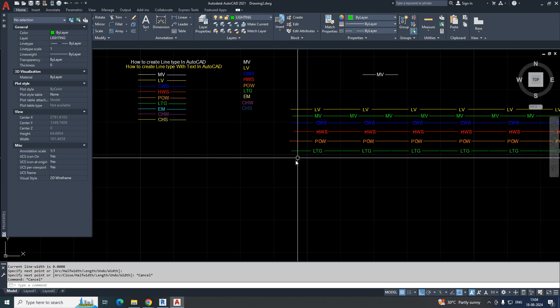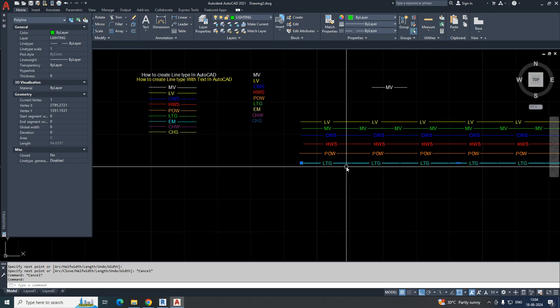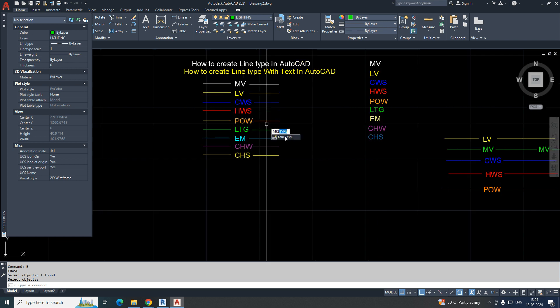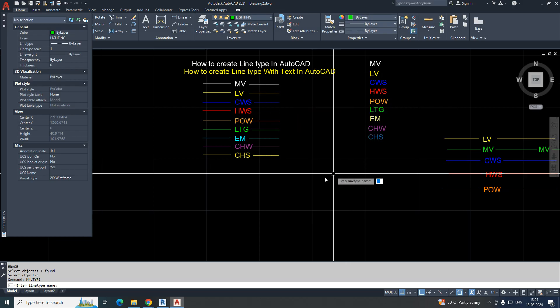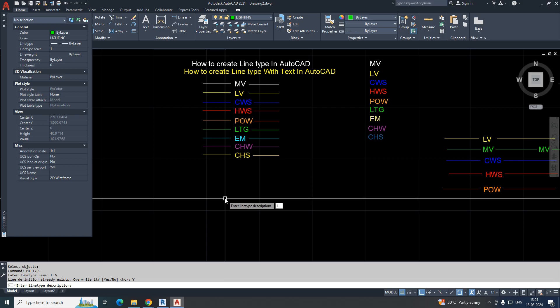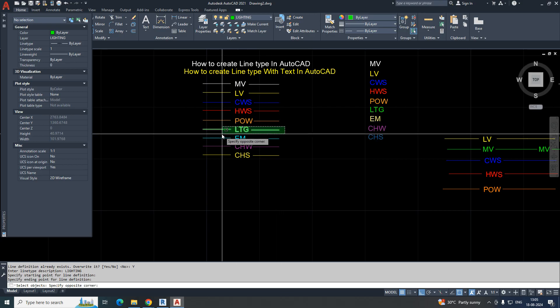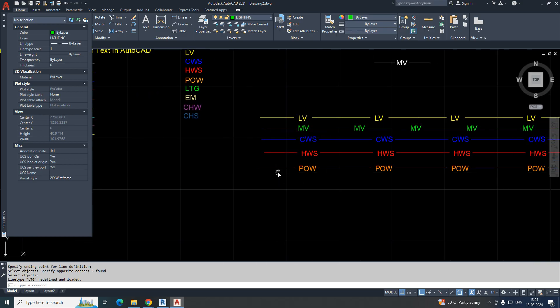Make the lighting layer current and draw a line — the line type will be created. If the line type doesn't look correct, it means you didn't pick the area exactly. Run MKLT again, replace the existing line type, give the name 'ltg,' enter the description 'lighting,' select the exact endpoints, select the area, and draw the line — the line type will be created correctly.